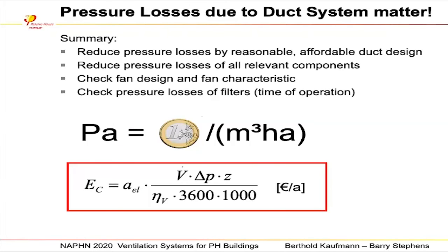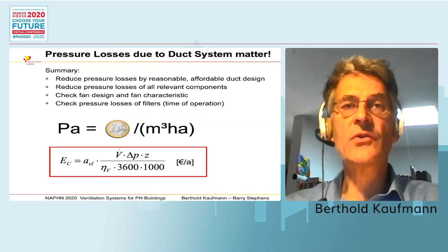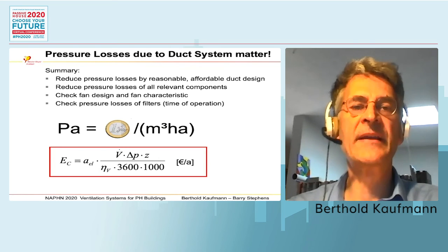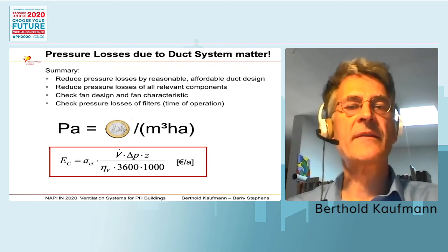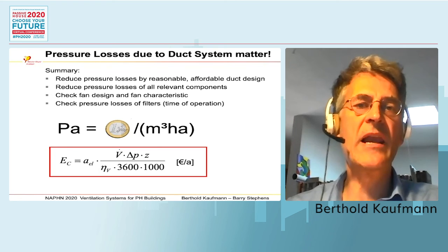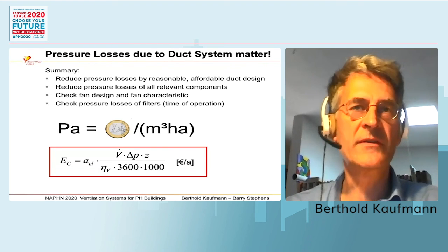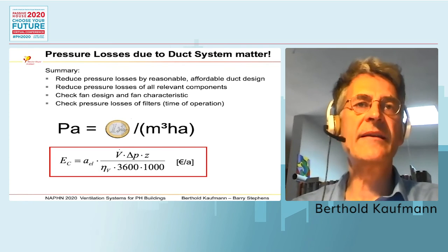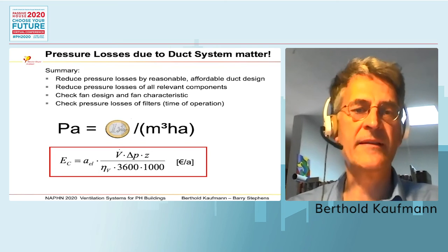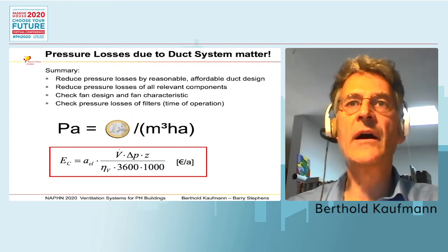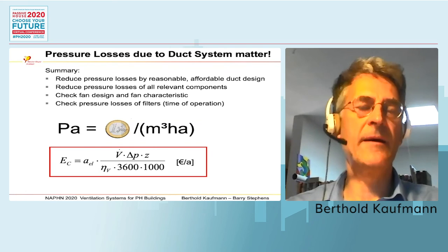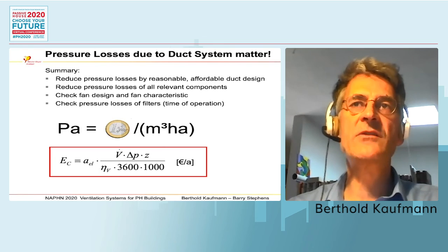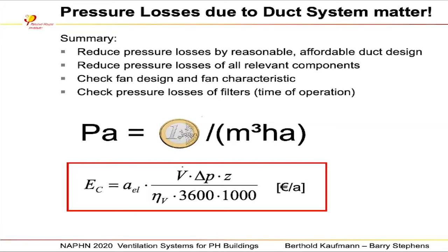Yeah. By the way, the effect of this reduction of the length of the pipes, you can check very easily in PHPP. So in PHPP, for every ventilation system, we ask for the length of the cold ducts in the warm area and vice versa. And you get very easily the number of the penalty, what you do bad with that. Okay, the next, just to show the numbers for what Barry explained with the pressure losses. Each Pascal of extra pressure loss is costly because of electricity, what you need afterwards for your system, and therefore you see on the next slide, please care for low pressure losses.